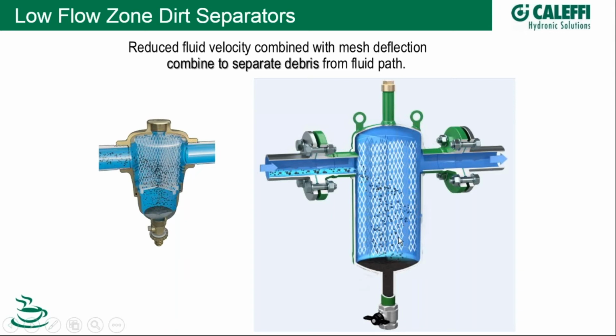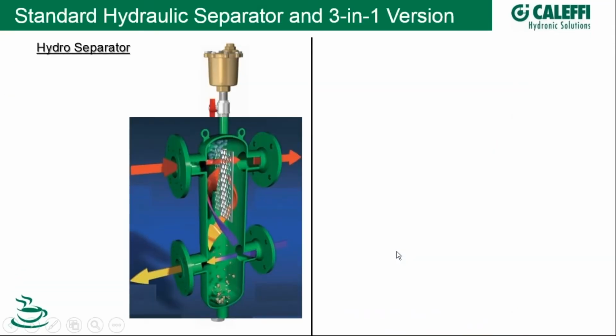And then lastly, you don't have to take these offline in order to service them. When you want to blow them down and open up the ball valve, there's no need to isolate them. Of course, you have to have makeup water to replenish anything that you purge off here. So that's low flow zone dirt separators.